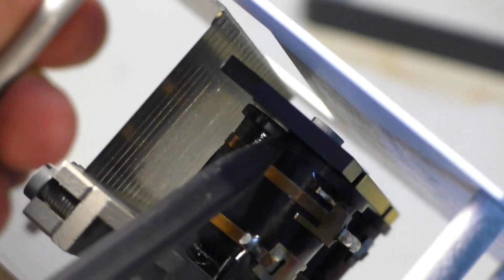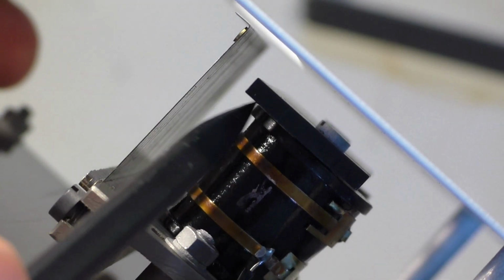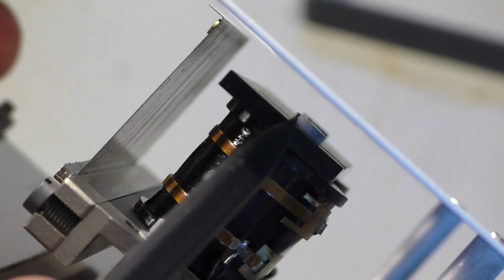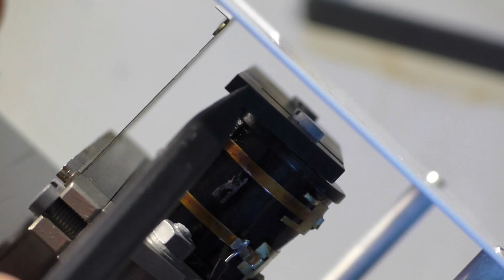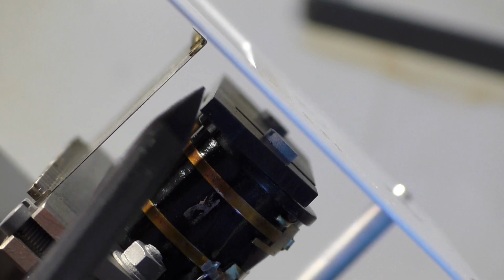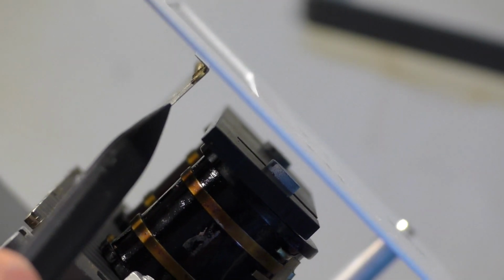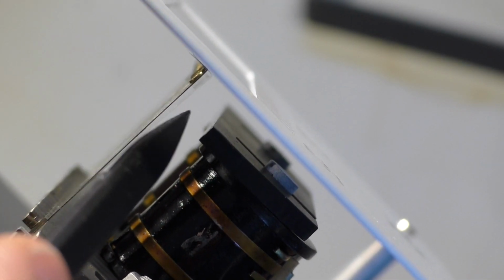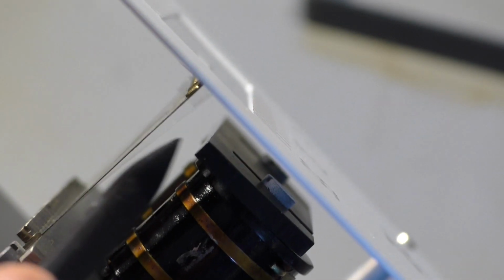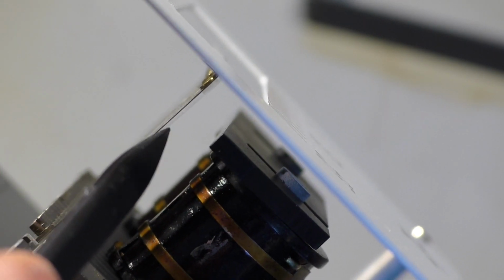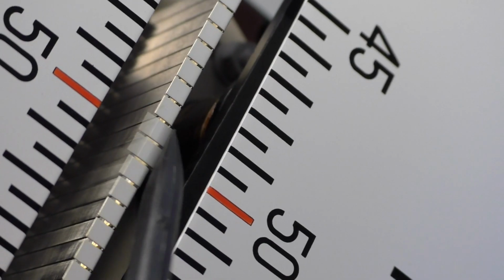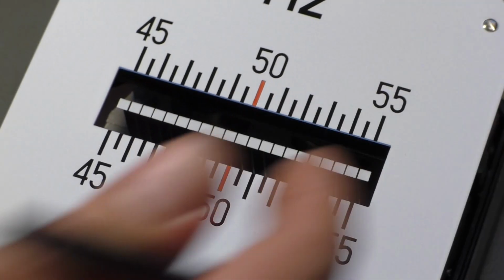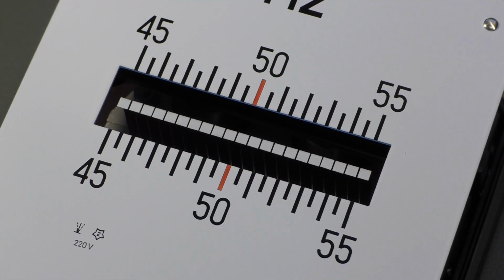Well, and that's it. Two coils. There's an iron or steel plate here that concentrates the magnetic force, and that attracts the steel reeds here and make them swing if the frequency corresponds with the frequency of the reed. And that's how this device works.